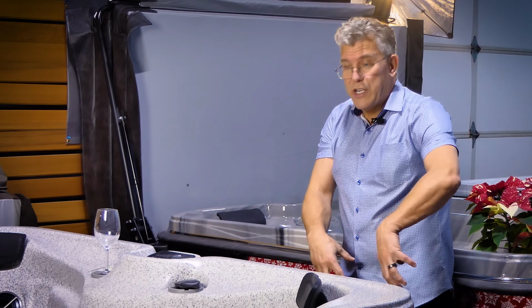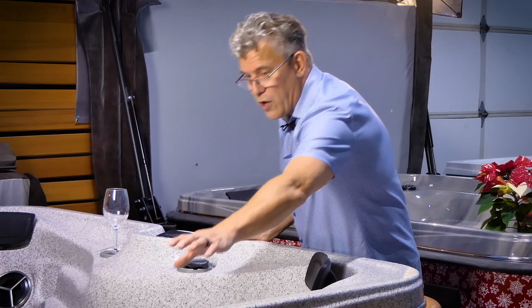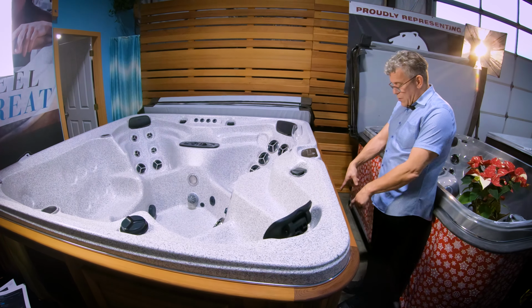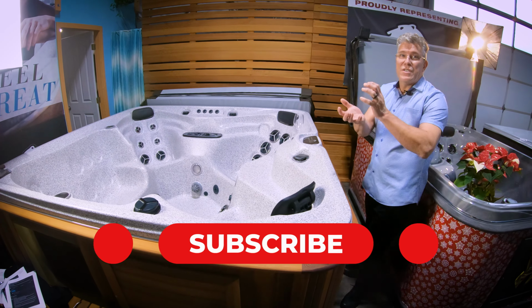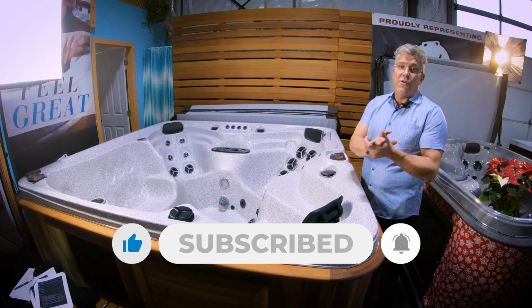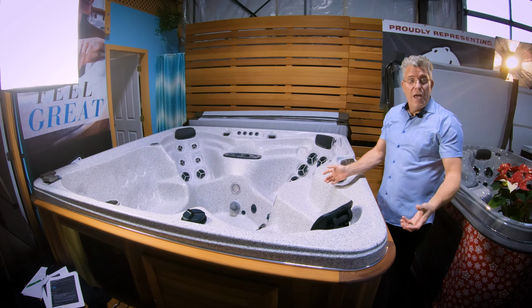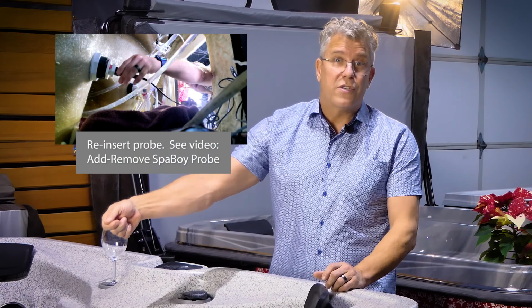I'll put my jets back in, secure all of my fittings, reattach the unions on the pump, open up my ball valves, and make sure it's ready to hold water, refill, then follow your startup procedures as if starting fresh, reinstall the probe, and you should be ready to go.